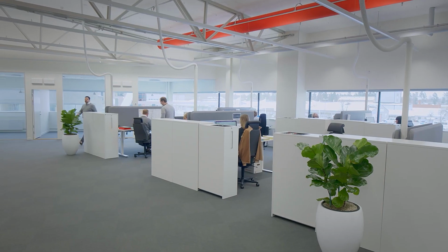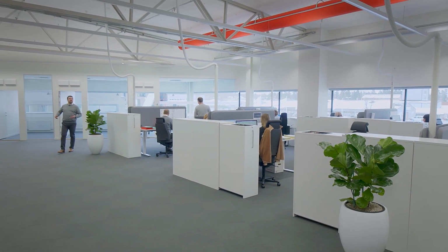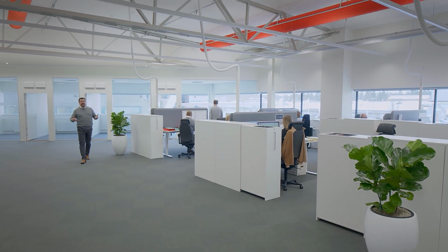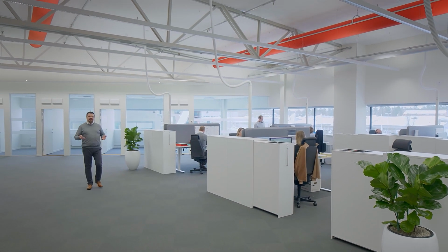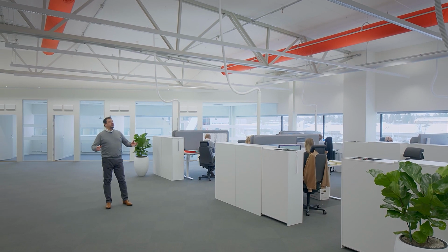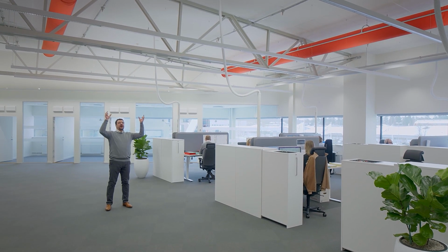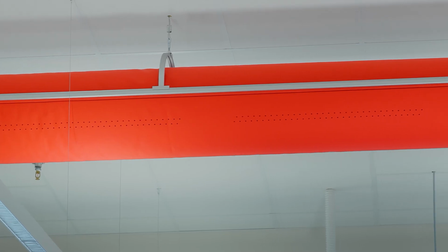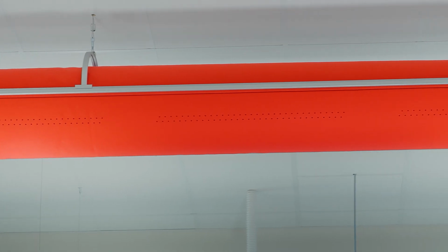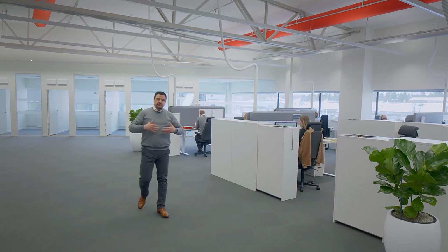So, if we now go out in the open office, we have solved the ventilation in the same way as we did in the individual offices. But instead of active diffusers, we have two long textile diffusers, and we control the airflow through dampers. Meaning that when there is more people in the room, we can increase the airflow, but also if the temperature increases, we can increase the airflow.